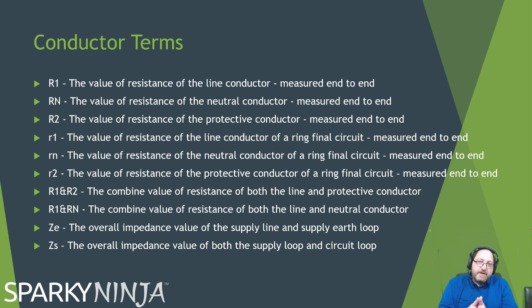The R1 plus R2 is a measurement of the line conductor, and maybe at the end it's been connected to the earth and the earth conductor back. So I'll connect the line and earth at one end, or the line and protective conductor at one end, and I'll measure across the other two at the other end to get a measurement of that circuit. R1 plus Rn, same thing, I've just connected line to neutral instead of line to the protective conductor. You'll see them used in a few tests' time.